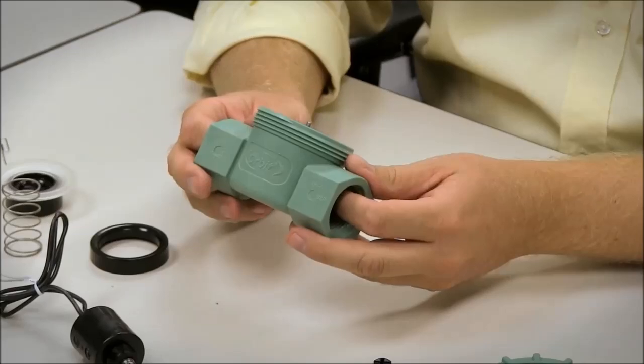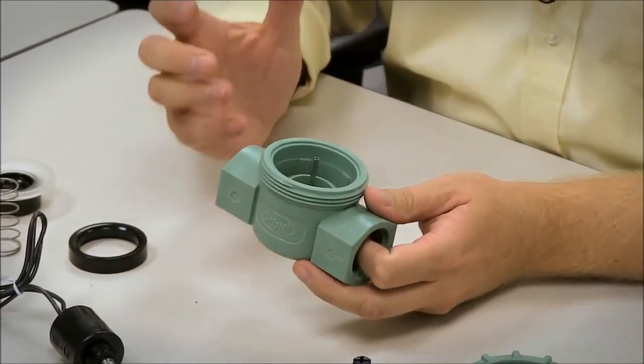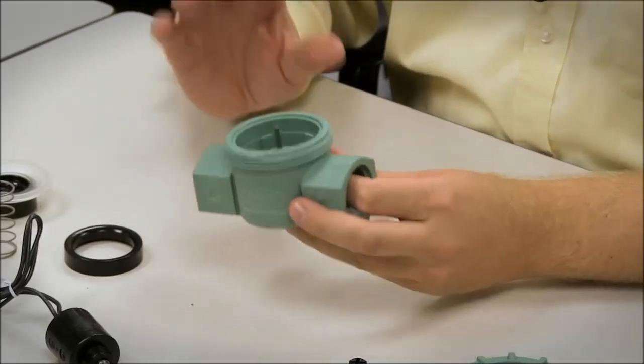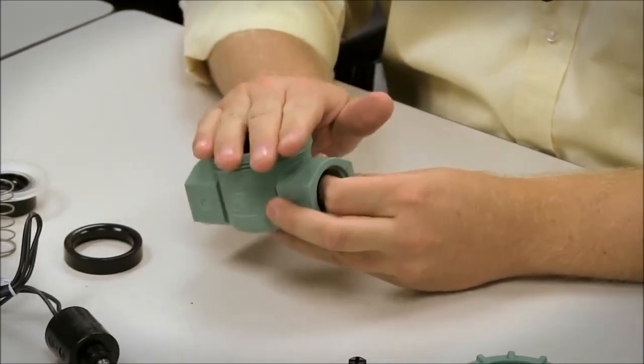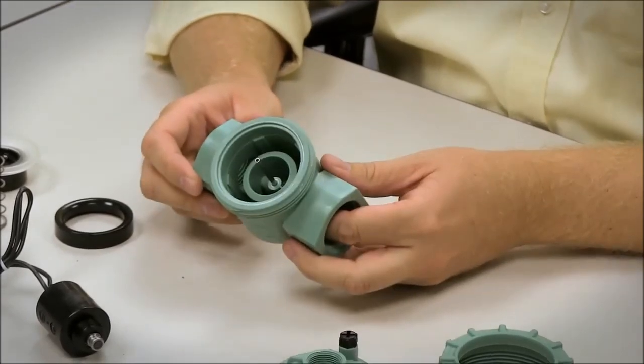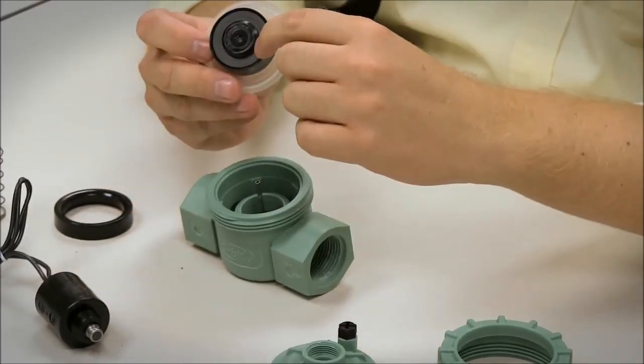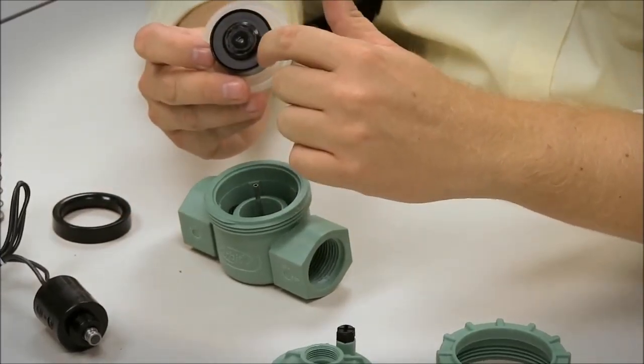And here we've got our valve body. So most of the common problems with a valve, one of the primary ones is debris inside of the valve. If you get debris in the valve, the valve doesn't function properly. Either it won't shut off or it won't run. What happens when it won't shut off is that you get debris trapped between this lip and the rubber seat on the bottom side of the diaphragm.